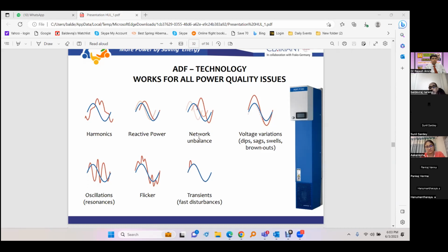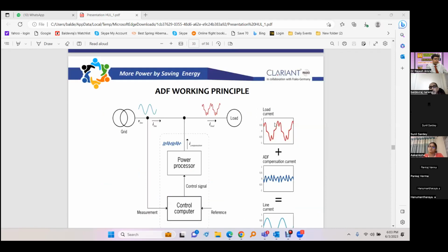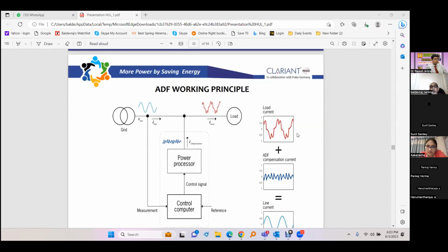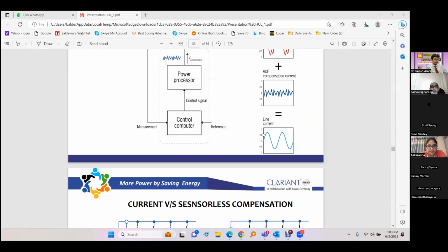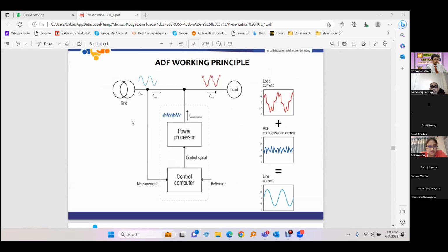Then suppose there is an unbalance, we can correct that also. We can take care of the voltage dips and sags. And that is what we are thinking, that we can take care of LVRT, HVRT situations, but this has to be designed to that level and it has to remain in the system, then only it can do that job. So this is how we are injecting the current in opposite. You can say there is a load current which has harmonics, and then we are injecting the opposite current to that, and the resultant current is normal sinusoidal current. So this is how it is working.